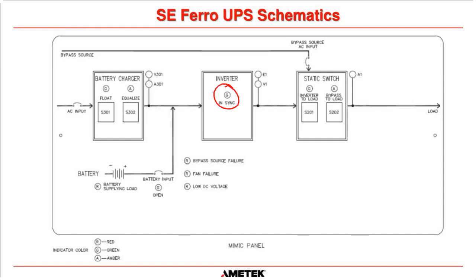On the inverter, we have this in sync light, and it is green, and obviously that should be on all the time because the inverter has to synchronize itself to the bypass source. And then on the static switch circuit block, we have S201, which is the inverter to load push button. Once again, the light is green, and we have a bypass to load push button, and the light is amber. And on this UPS, they only bought 3 alarms as part of their alarm package, and that is bypass source failure, fan failure, and low DC voltage, and all 3 of them are red LEDs. So if they're on, that's telling you that you have a problem. But once again, this is an exact representation of the front panel of your UPS.